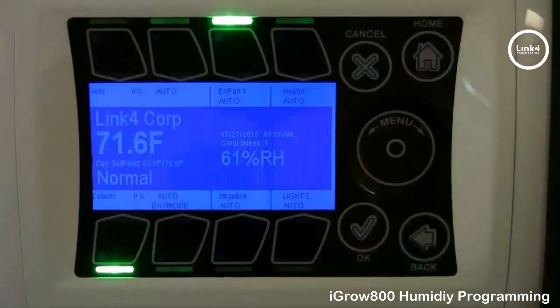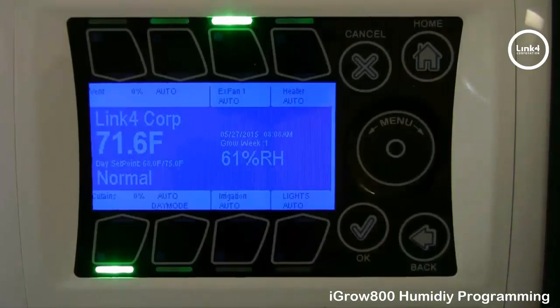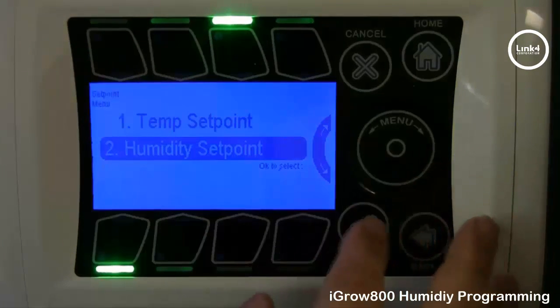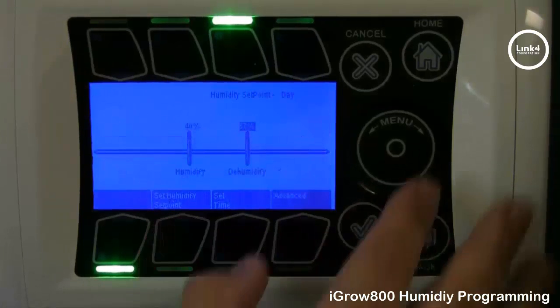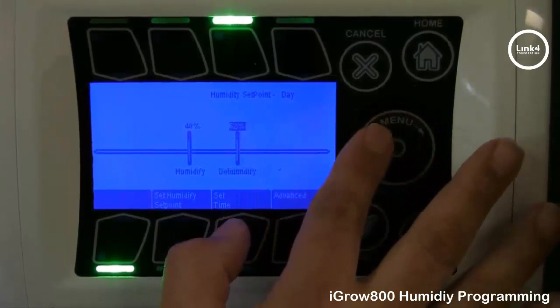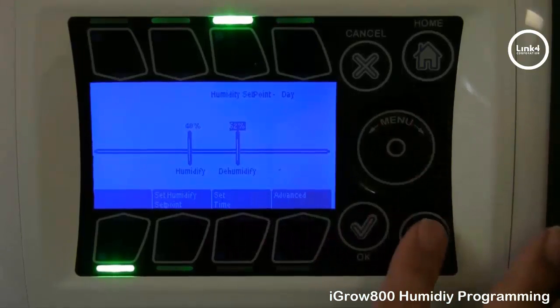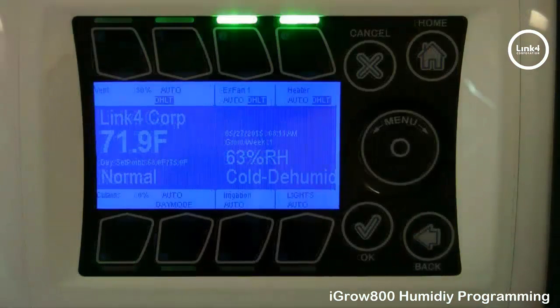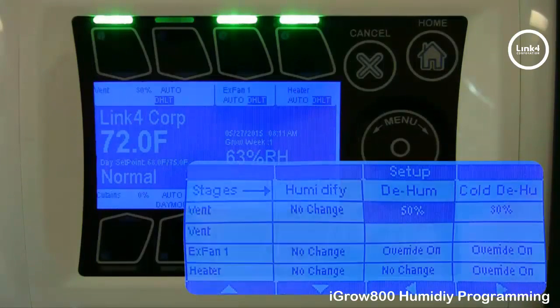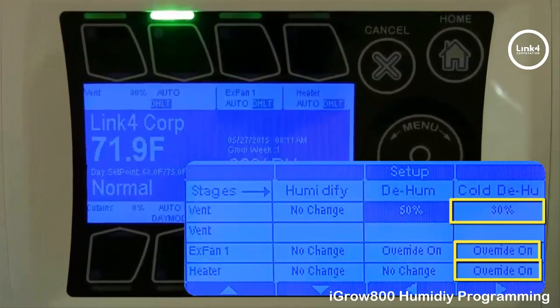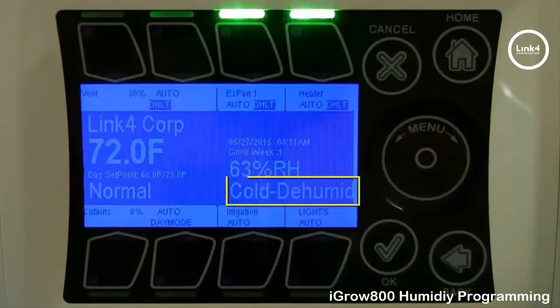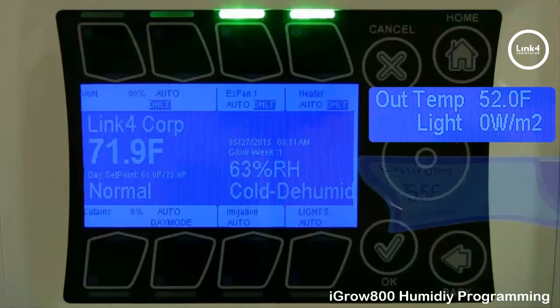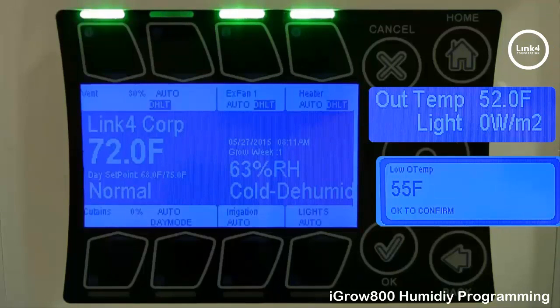Let's put this controller to the test. Hit the home button, and we're going to force this controller into a humidification state by hitting OK, going to set points, then humidity set point, and the day set point. We'll decrease the dehumidification value to 62%, hit OK, hit back to save the changes, and hit the home button. As you can see, the vents, exhaust fans, and the heater are all cycling because the controller is currently in a cold dehumidification state, because the outside temperature on the controller is 52 degrees, and our threshold is 55 degrees.